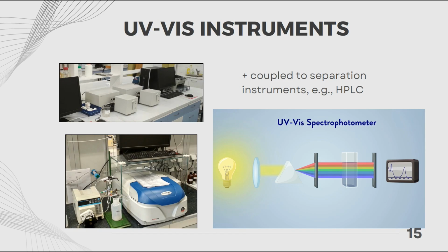Monochromator means that you may leave only a specific wavelength of light. It may be helpful in the UV range. We usually select only one wavelength of 230, I guess. You may leave only one wavelength or the whole spectrum, visible, ultraviolet. So you have this schematically as the prism. Then the cuvette with the sample, the same cuvette, and then the photodetector, which measures the intensity of light that passes through the sample. Okay, I guess that's clear.